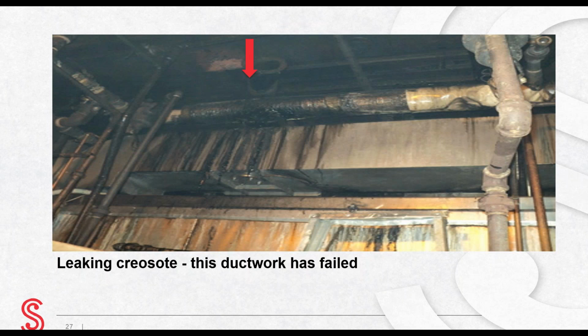This is a large indoor meat smoking oven that has ductwork that is not NFPA 96 Type 1, and the ductwork has failed. It is leaking grease onto the building's HVAC duct behind it and below it. We've added an arrow to make it easier for you to see the failed duct. This ductwork is not liquid tight, and creosote is leaking outside of all the ductwork. Liquid tight ductwork does not allow water vapor, grease vapor, or creosote vapor to leak outside the ductwork. If there was a smoke or fire, the creosote that has leaked would cause the fire to burn hot and spread fast in the building.